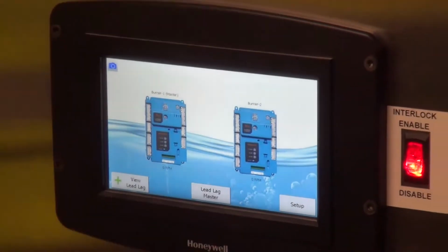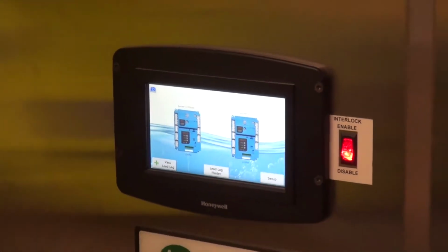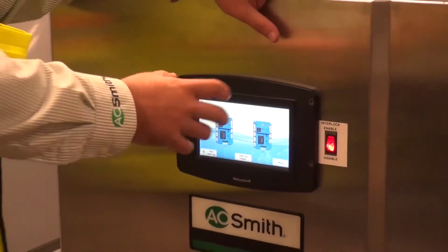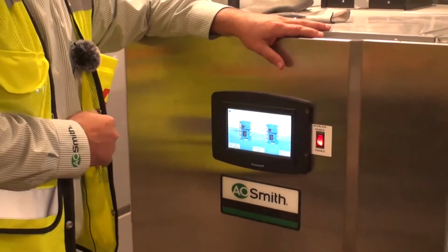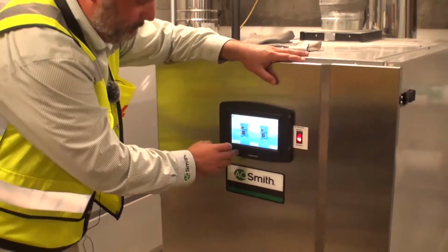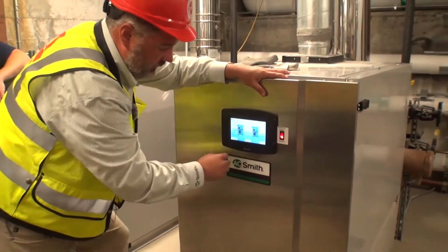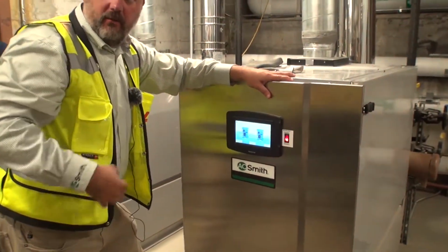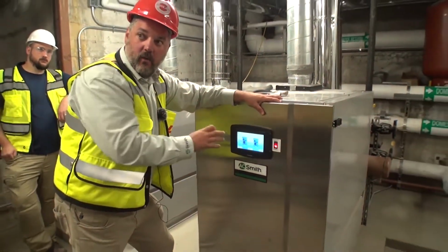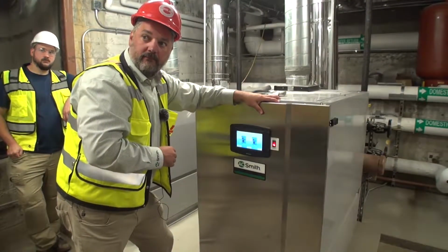What am I going to be looking for if something goes wrong with one of these? Because the other one's going to catch up and control it if one's down. You'll see an error. It'll actually go yellow with an error code on the unit. I'm looking at the unit screen then. Yep. It'll show you, uh-oh, that burner's not in sequence, it didn't kick on. We've got an error flashing. So I'll be seeing flashing on those ones. Correct.